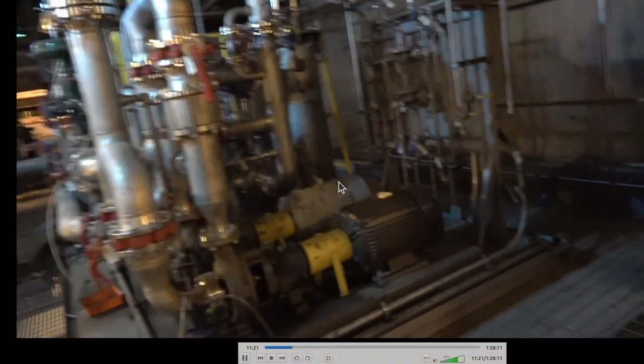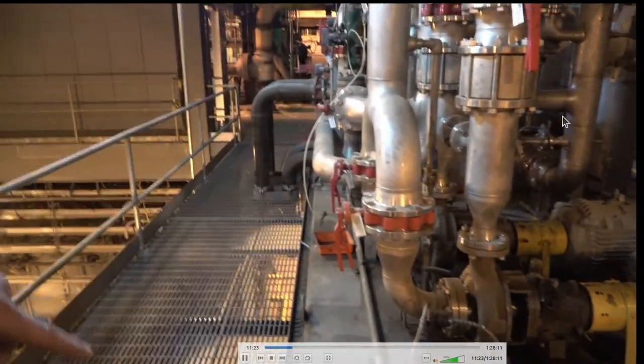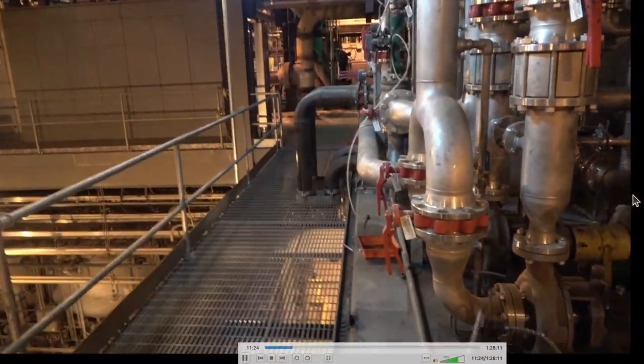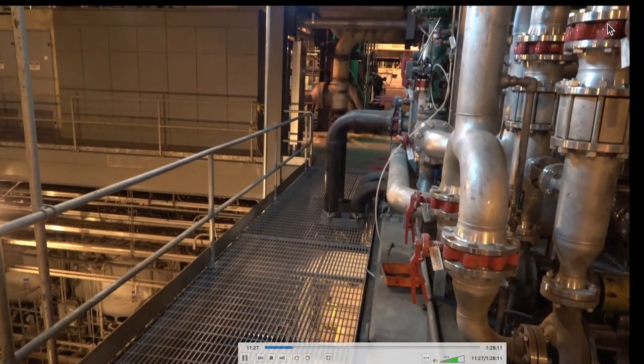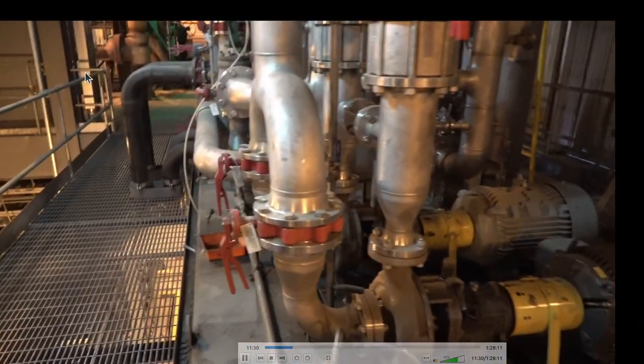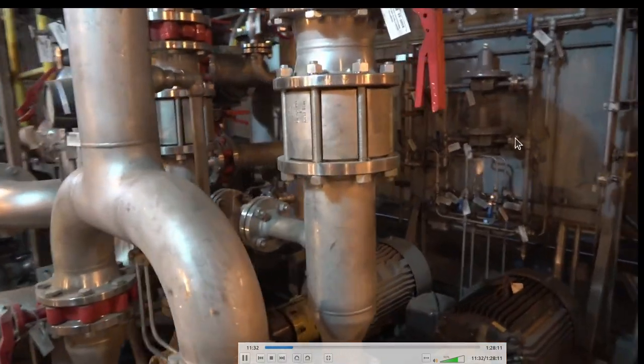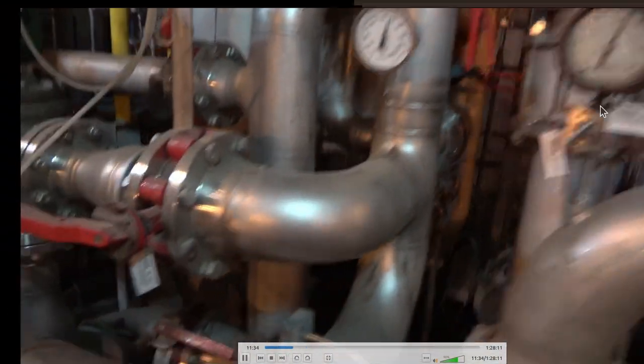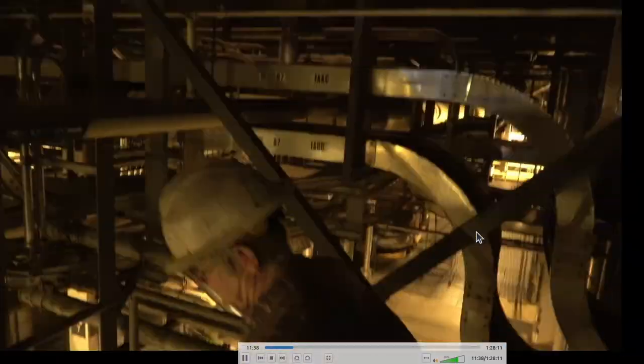Down here are the polishers, and here's a generator cooling skid. You have your two pumps. The resin bed sits here. Some plate heat exchangers sit back here. This measures any air coming out of the system so you know if you have a hydrogen leak. The water is lower pressure than the hydrogen, so for many leaks the hydrogen will leak into the water side.